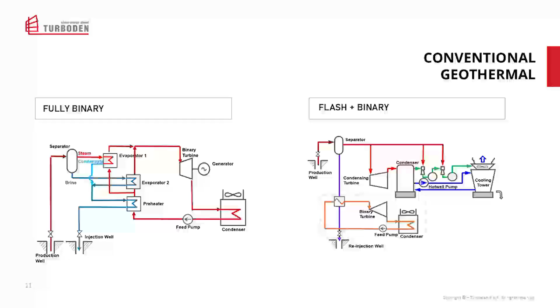We already heard a lot about conventional and non-conventional applications, and we want to mention that we already have experience in all of the applications of the binary system discussed yesterday and this morning. In a traditional application, a full binary system is typically the most straightforward solution, meaning that the ORC is recovering 100% of the geothermal source coming from the ground. That means the geothermal resource is separated into steam and brine, which are both conveyed to the ORC to produce electricity. However, there are many traditional flash steam turbines in the world that only use the steam portion. What the ORC can do is use the brine dismissed by these former power plants to add other power, as we'll see later.